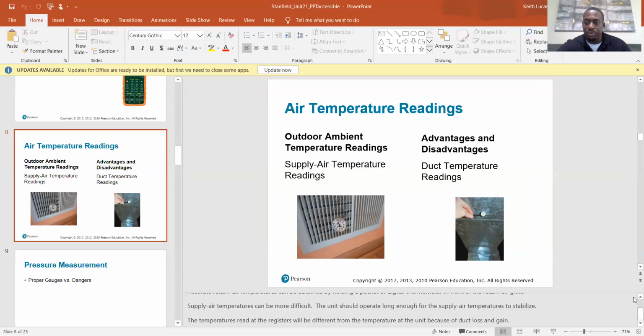So what they mean by that is if you check your temperature right at the plenum, right as it's leaving the evap coil, it's going to be colder than when you check at the vent, which is at the end of the duct run, because typically it'll be a little warmer, and not all the time. Well, yeah, it'll be at least a little bit warmer, and that's because as the air travels from the plenum all the way through the duct and then out of the supply vent, it's going to pick up some heat. The ductwork being in that hot attic, even though it has a thermal barrier on it, which is the insulation, it's still going to pick up some heat. That thermal barrier resists heat. It doesn't completely 100% eliminate any heat gain in that duct. So with that being the case, the air coming out is going to be a little warmer than the air going in.